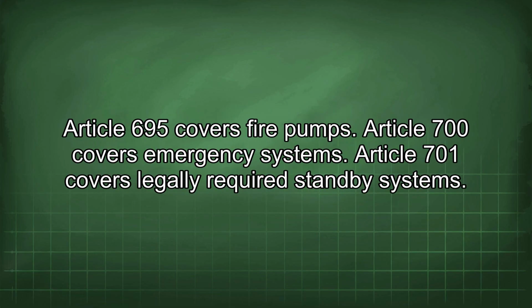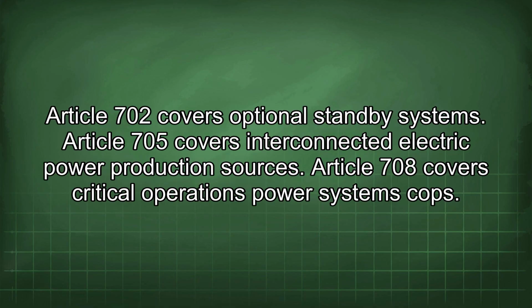Article 695 covers fire pumps. Article 700 covers emergency systems. Article 701 covers legally required standby systems. Article 702 covers optional standby systems. Article 705 covers interconnected electric power production sources.